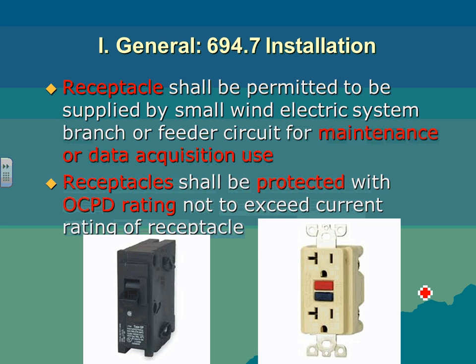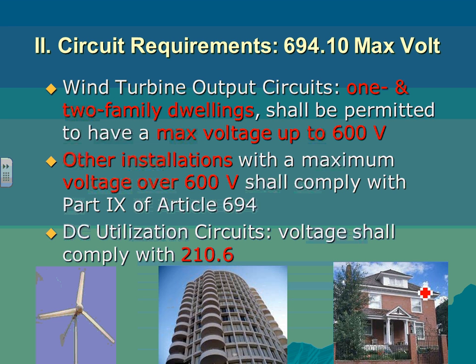So this one allows you to have an overcurrent protection device protecting a receptacle that you can use for maintenance or collecting data right next to the tower. That's a nice article. Voltage limitation: what's the highest voltage that you can get out of this tower? If you're doing non-dwelling, the limit is the sky. You can get 750 volt.